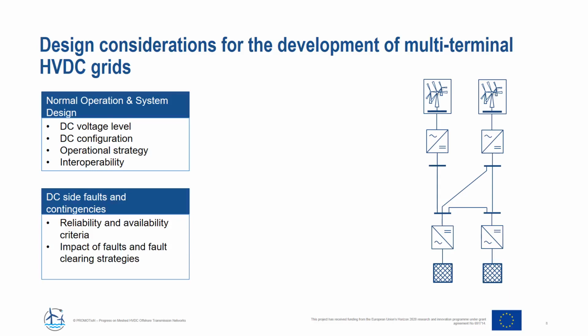Moreover, it has to be defined how DC side faults and contingencies are treated. So what are the applicable reliability and availability criteria for those DC grids, and what is the impact of faults and fault clearing strategies on the overall system and the components? There is no standard fault clearing yet, and this leads to different options also within the grid codes on how to define the DC fault ride-through, for example.